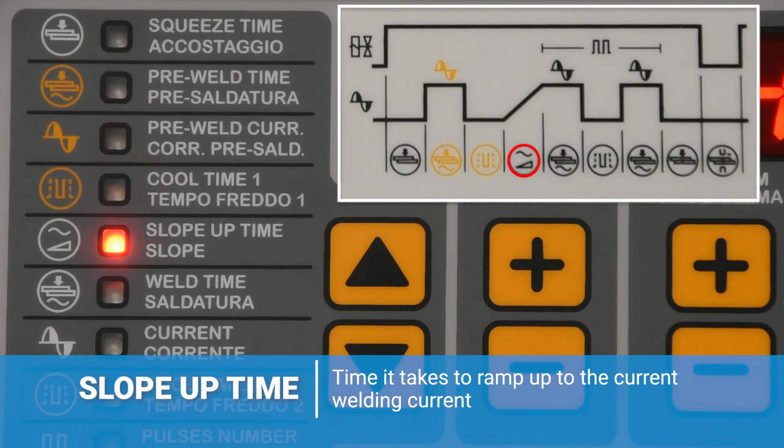Next, we have the slope up time or upslope time. This can be set between 0 and 25 cycles and is the time it takes to ramp up to the main welding condition.